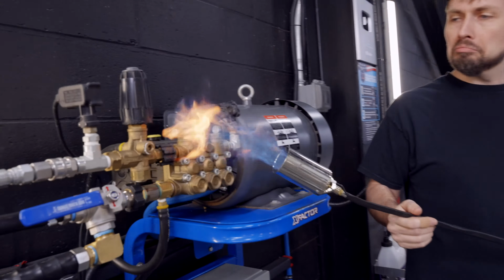So this is supposed to idle and then time down. Oh, the white wire's got to go up in the top corner to give the time delay relay power. This is why I recommend to cut the wires in place and not slide these off, because it's easy to put them on backwards again, then you have another weird problem. All right, fire it up now. That should have power. Yeah, so now you have time delay off. I tried to pull a fast one on you and you caught it right away.